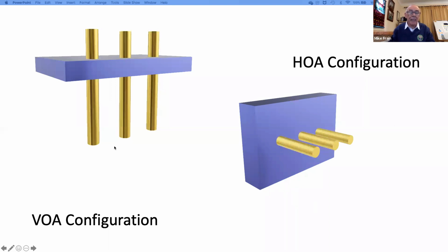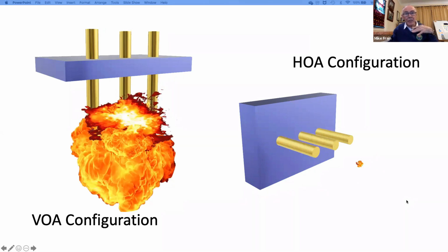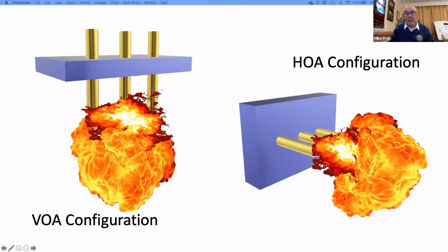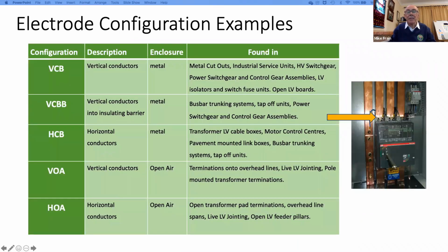And then the next ones are in air. The first one, VOA, is in air configuration, and HOA is in air, but a horizontal configuration. VOA was in the 2002 edition, by the way. The HOA configuration is similar, but as you can appreciate, the thermal effects radiate out towards the worker in the case of the horizontal configuration, and tend to be a little bit more aggressive. So this is just an extract from the guide, but I wanted to show you what a VCBB one looks like in terms of something in the flesh. So if you can see there, you've got an air circuit breaker, and the conductors terminate directly onto the top of the, in other words, straight into a barrier.